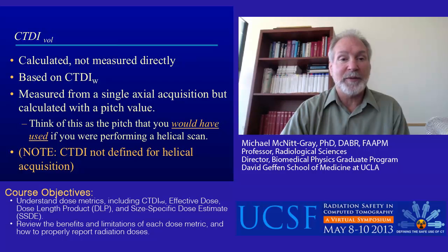CTDIvol is a calculated value. It's not measured directly. It's based on that CTDIw of the previous slide. It's measured from a single axial acquisition, but it's calculated with a pitch value. So you have to think of this as the pitch value that you would have used if you were performing a helical scan. That's typically the pitch value from the helical scan protocol.